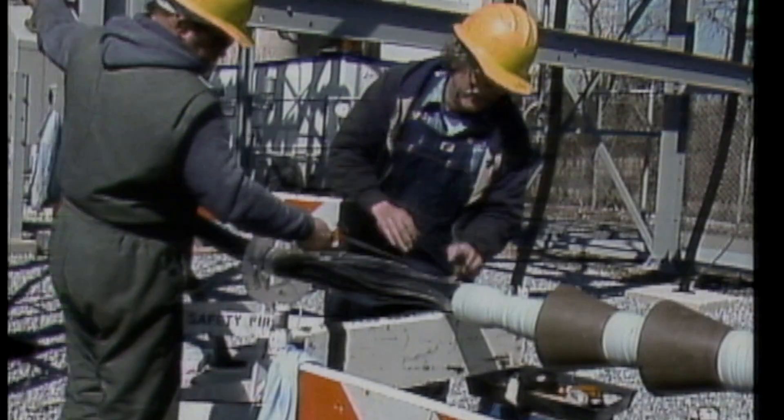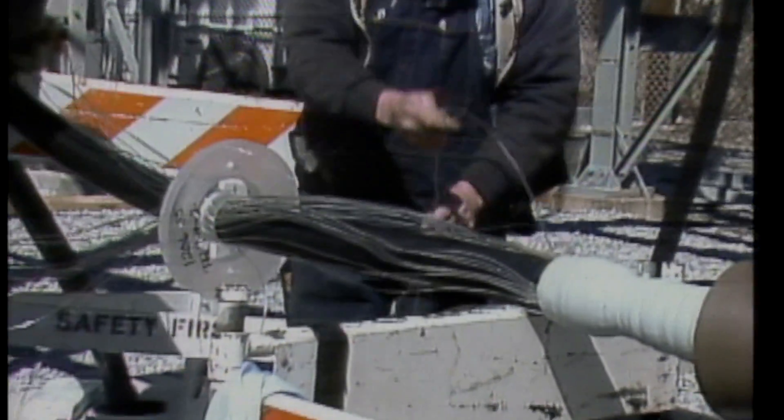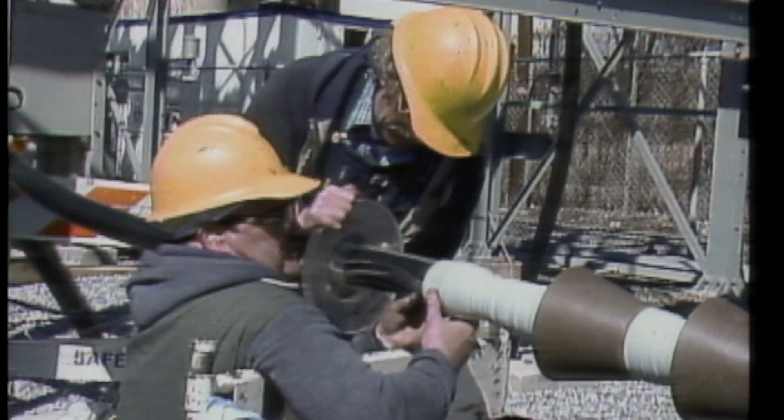When the termination is completed, the tinned copper wire braid and the neutral wires are carefully threaded through the plastic bushing at the bottom end of the termination connection. And the bushing is slid up into position.